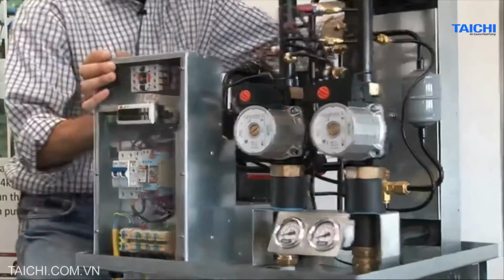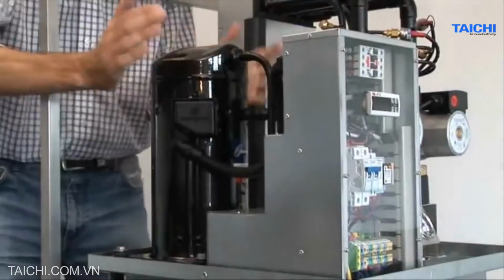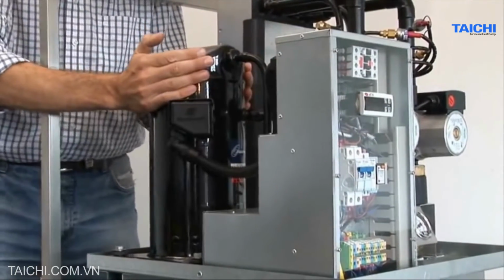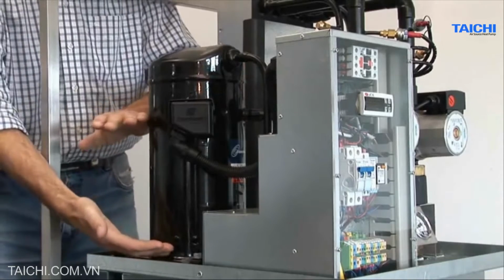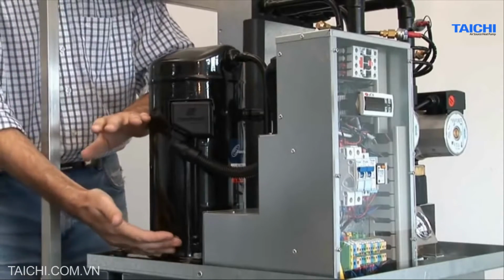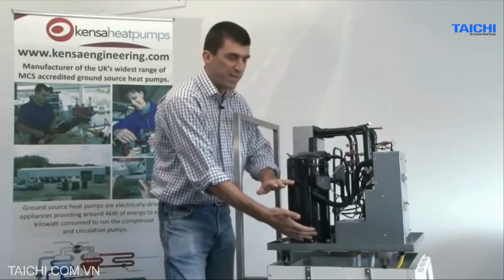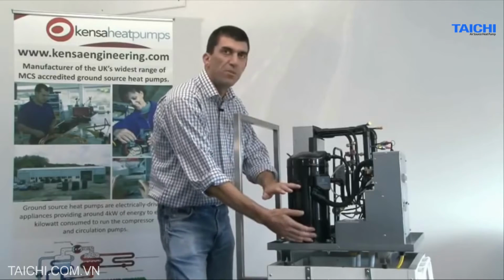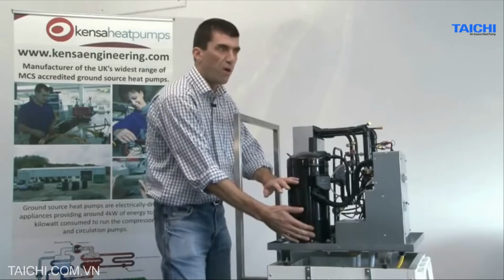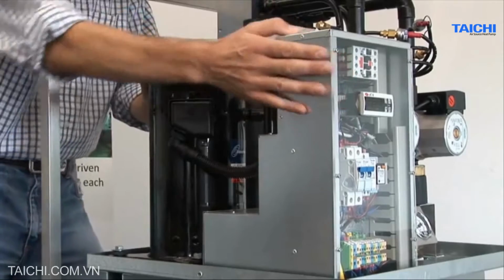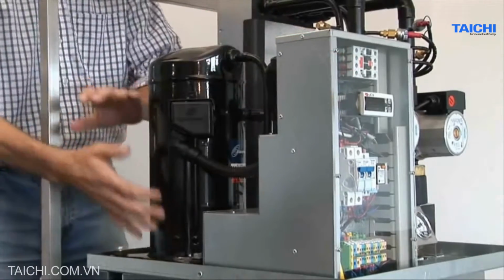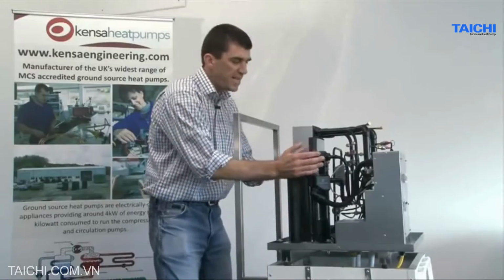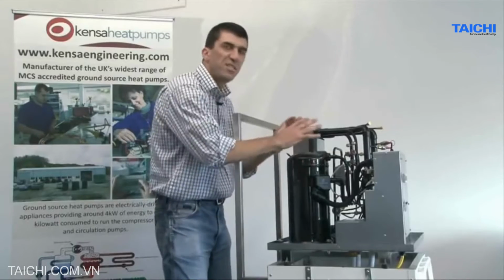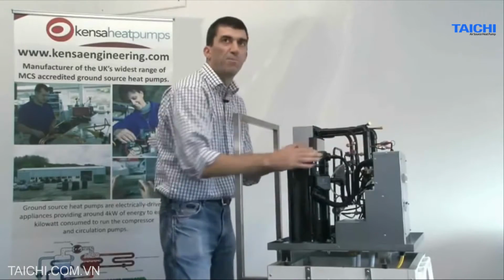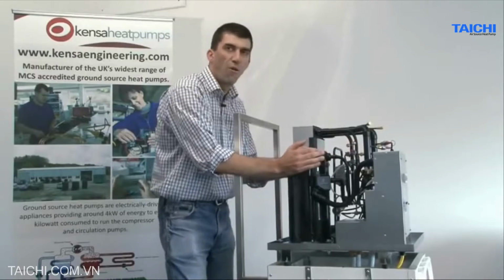Let's see what else we've got. This is the main component of the heat pump. This is the compressor. The bottom 2/3 of it is an electric motor. It's either on or off. In a Kensa heat pump, there's no variable speed. They just either run or don't run. The job of the electrics box is to decide when to run the motor. If there's a demand for heat and if the safety systems all say go, then the electrics box simply turns the motor on and off.